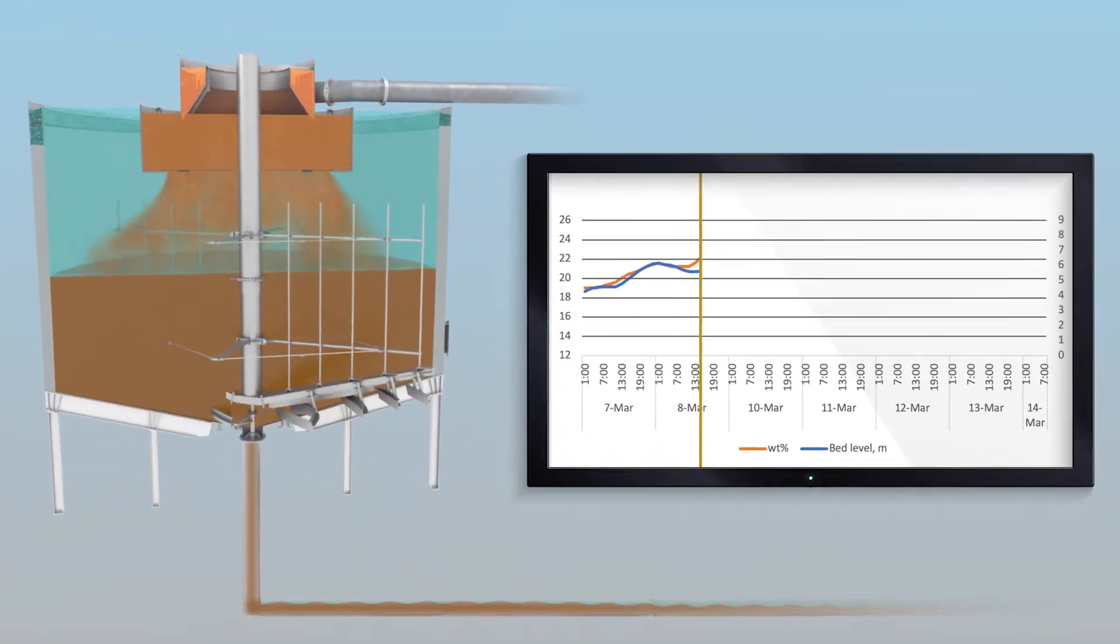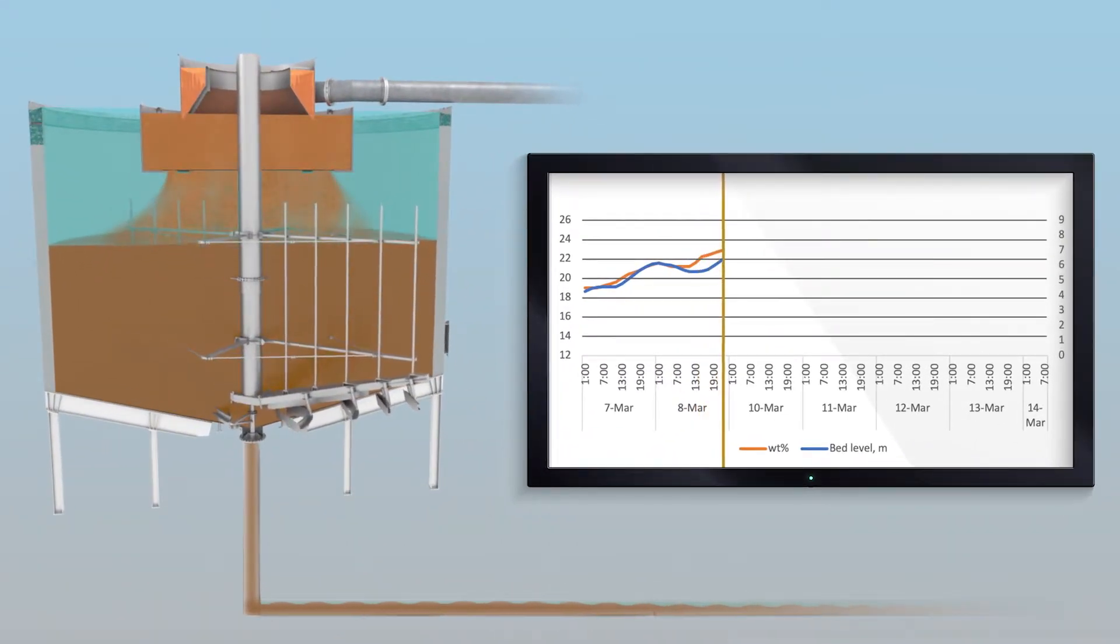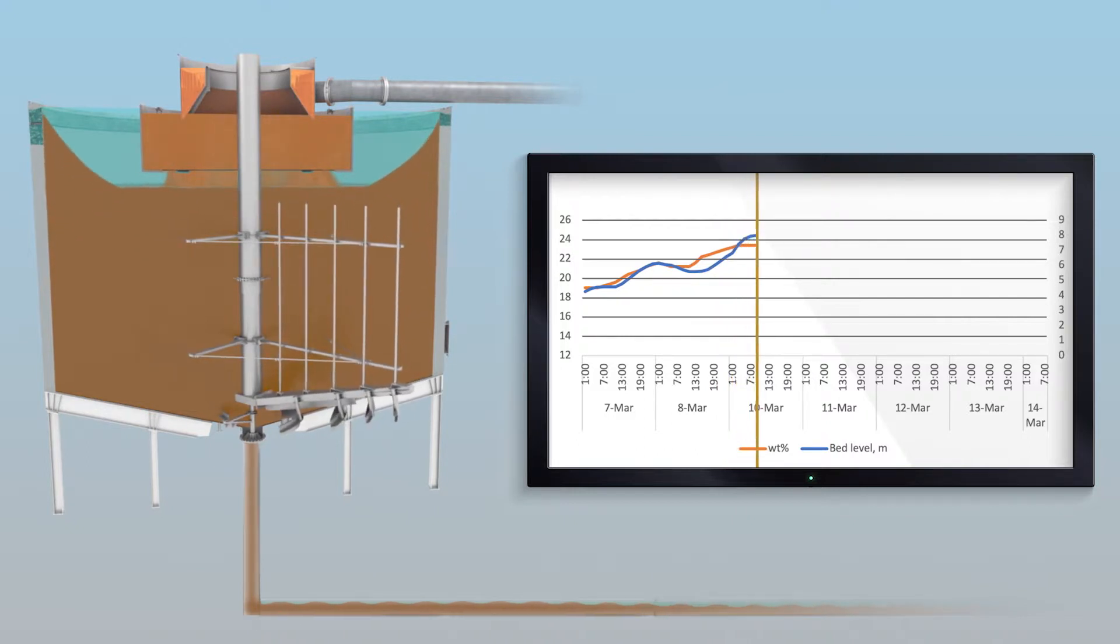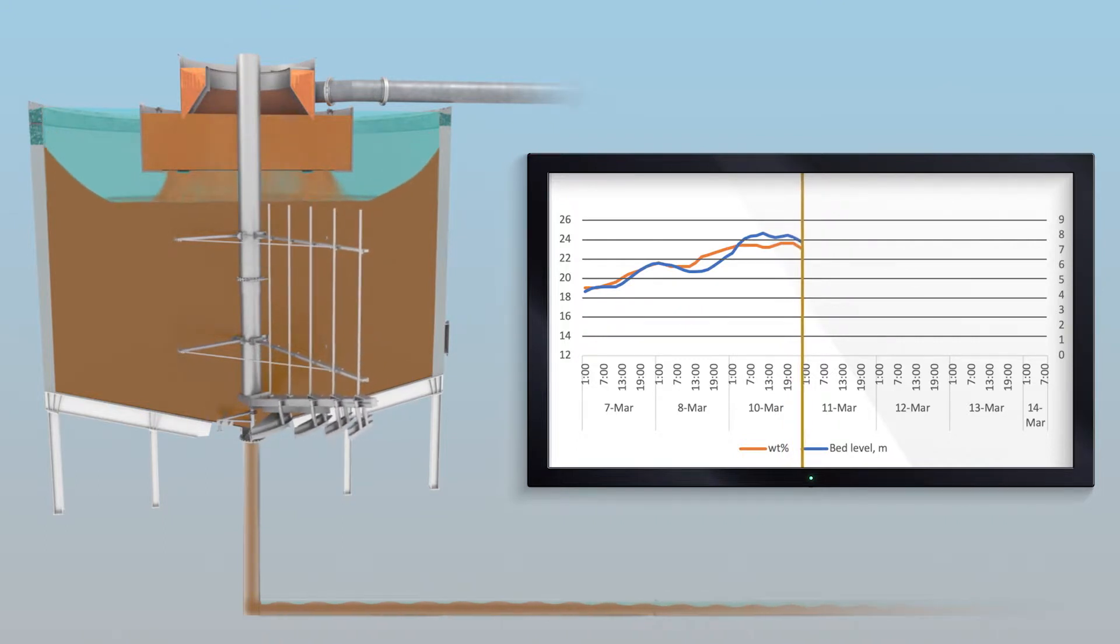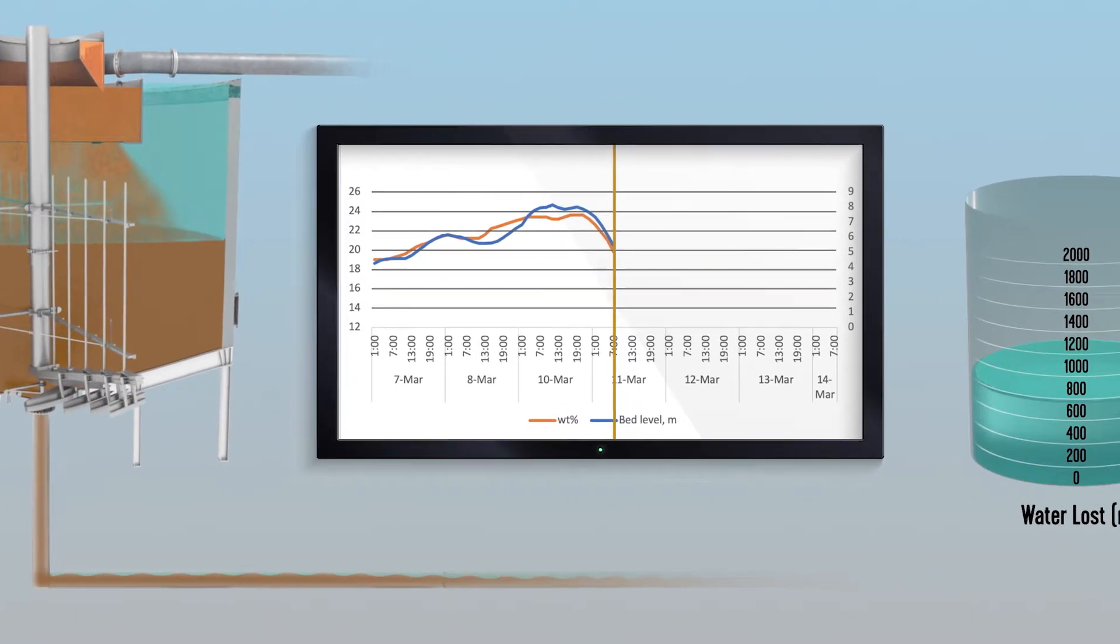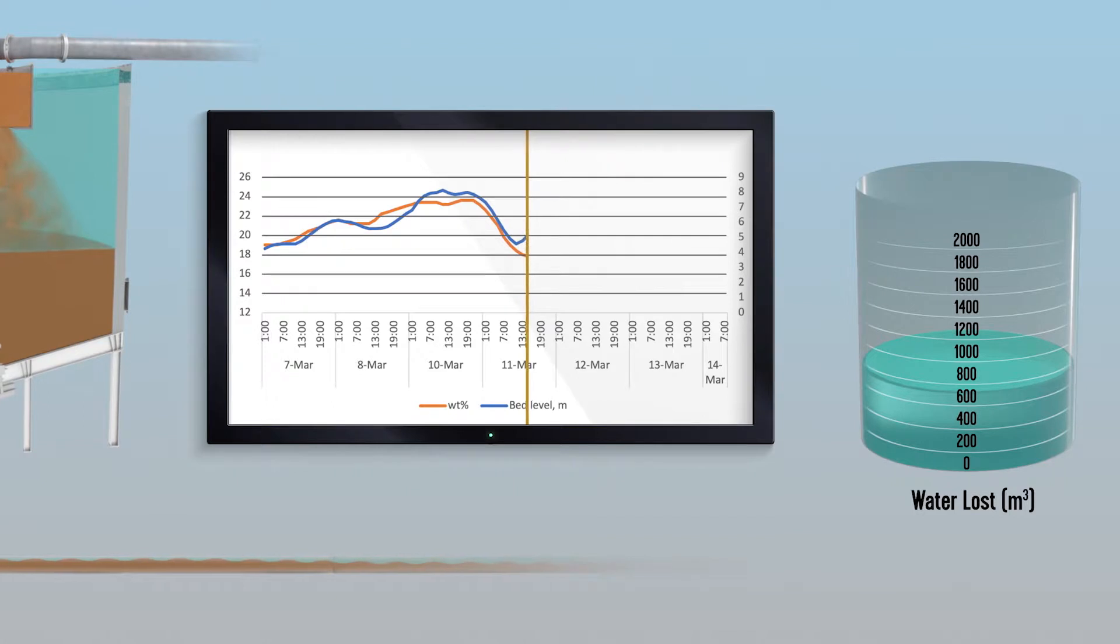In this high-density unit, for example, the bed level is fluctuating. When the bed level is too high, solids spill over into the launder. When the bed level is allowed to vary, the underflow lacks consistent density, causing significant water loss after just a few days of operation.